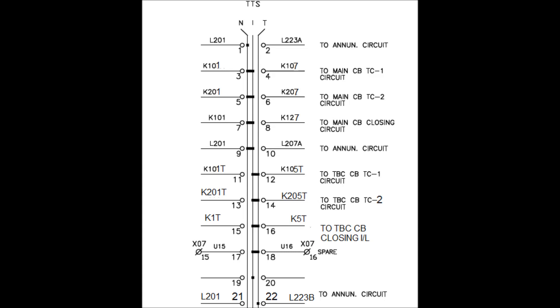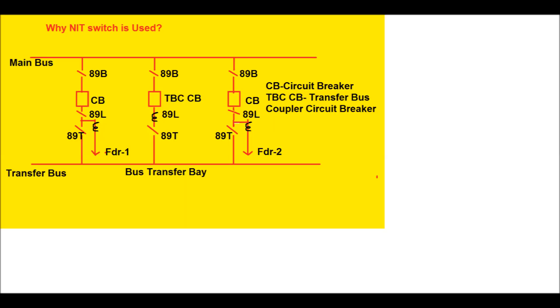For the Inter-Transfer position there are again four contacts: 11, 12, 13, 14, 15, 16, 17, 18. Contacts 11 and 12 are taken for the TBC CB TC1 circuit for Inter-Transfer position. Contacts 13 and 14 are taken for the TBC CB TC2 circuit, and 15 and 16 are taken for the TBC CB closing interlock circuit. Contacts 17 and 18 are spare contacts. Contacts 19 and 20 are only for Inter position and are not taken for any use. Contacts 21 and 22 are taken for the annunciation circuit — the contact for Transfer position.